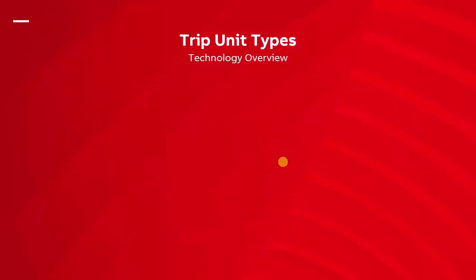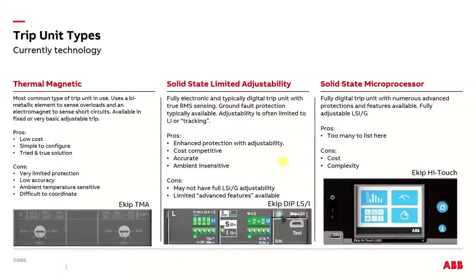Okay, let's get into the trip unit types, the basic technology overview of what they are. I broke this into 3 types, and there definitely could be some argument about the last 2, but I broke it into thermomagnetic, and that's pretty cut and dry, and then solid state with limited adjustability, and then solid state microprocessor. So let's start with the thermomagnetic. By far, this is the most common type of trip unit in use, because virtually every circuit breaker that you see, all residential, lighting panels, appliance panels, all those contain thermomagnetic breakers most of the time.